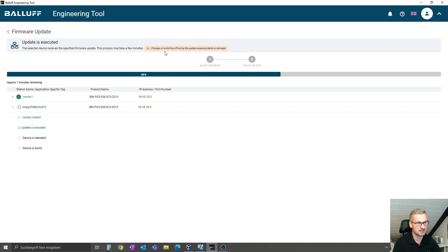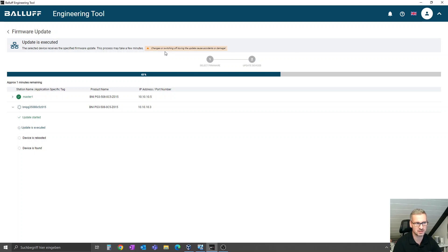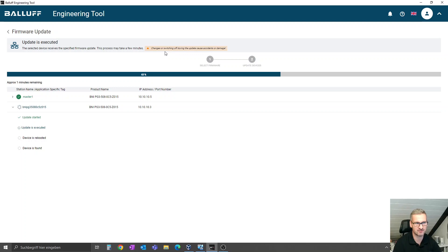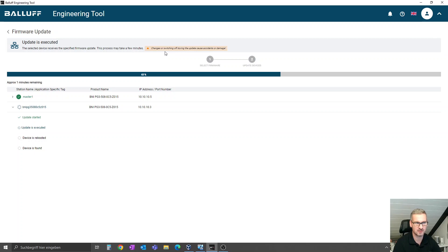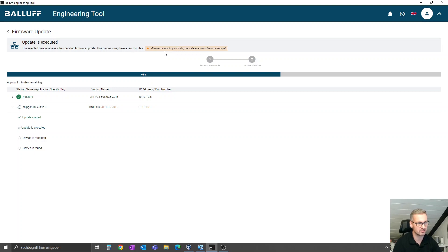You see the first one is already done. The second one has also started. It makes it sequential—that means the first, then the next, and so on. Because if you have them aligned to each other with the network communication, it makes a double restart, and at that point you will lose the communication to the other connected devices and the firmware update may fail. This is the reason why the software makes the firmware update master per master.